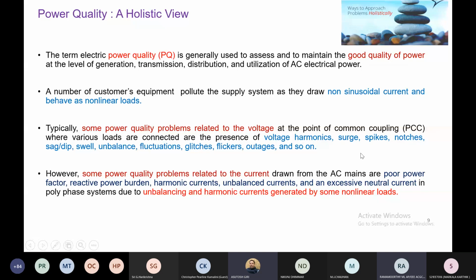There should not be any surge, spikes, or notches in the voltage. If these are present in the voltage waveform, they can be very harmful to the load. If it is a critical load, suppose a ventilator working with the supply system, and the voltage and frequency are not maintained constant, it may create problems, because ventilators support critical patients. So these things are very important, and nobody can deny the importance of power quality.